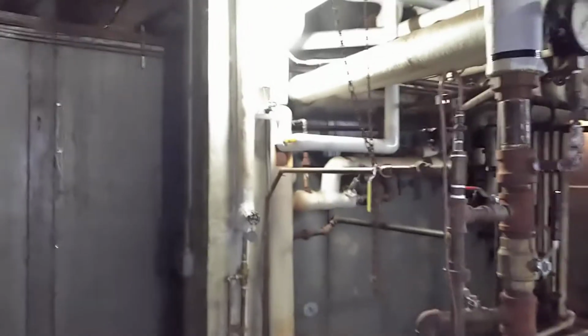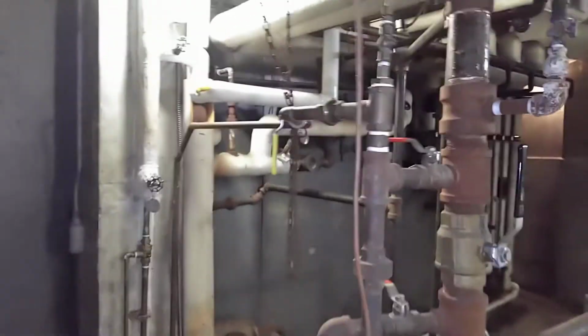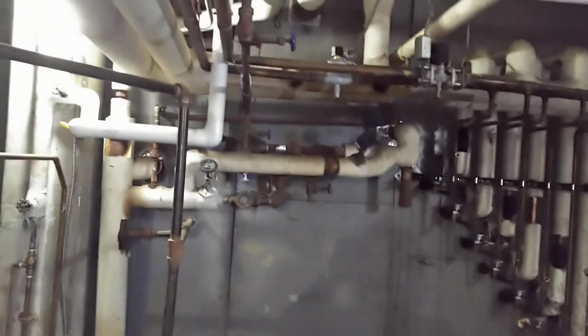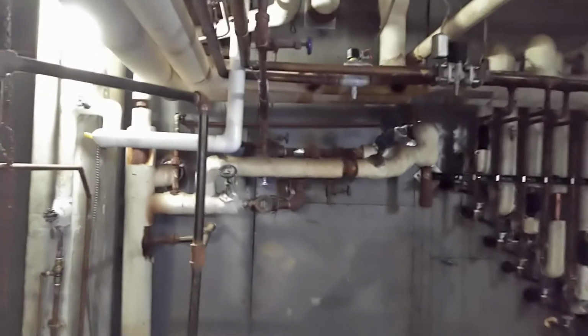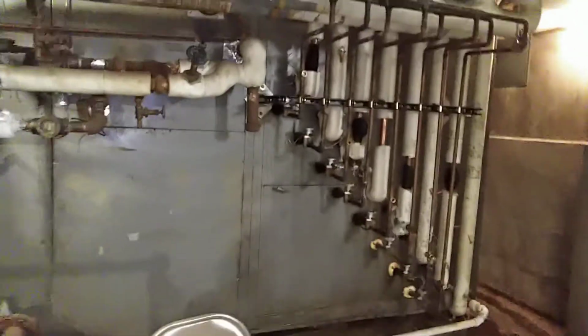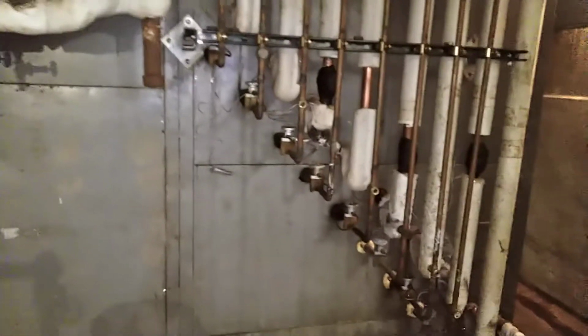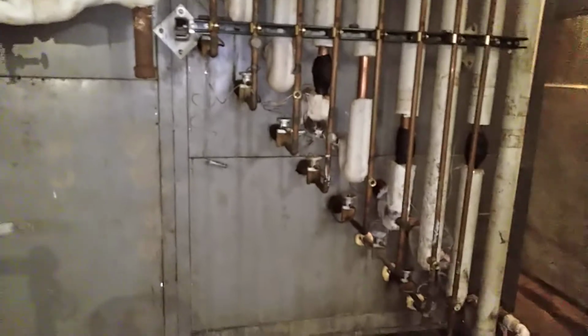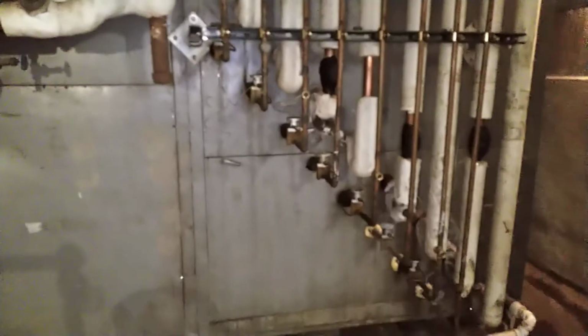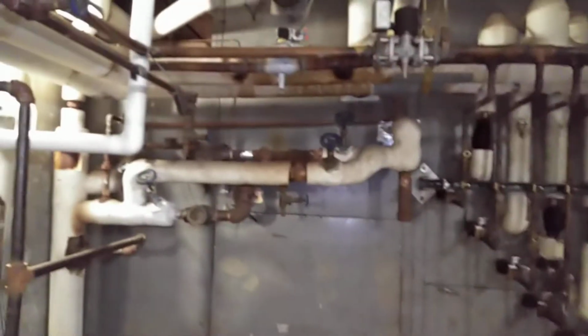There's a single fan in the system. There are return air and outlet air dampers to provide for fresh air and economizer air into the system. The hot deck is usually either a steam or hot water coil, but can be anything that heats air. The cooling coil is usually either a chilled water coil or a direct expansion refrigeration coil. On this particular unit, we have a direct expansion refrigeration coil and we have a steam coil.